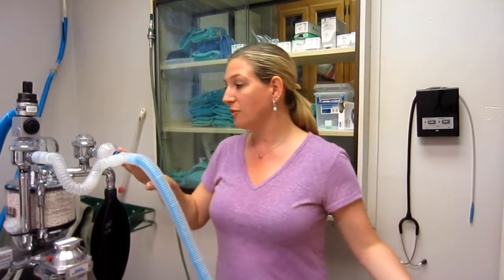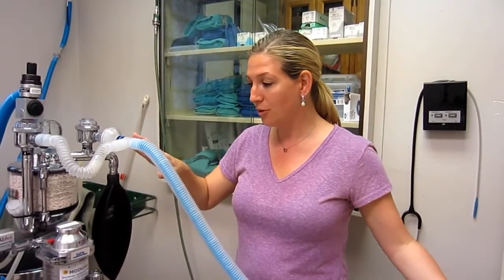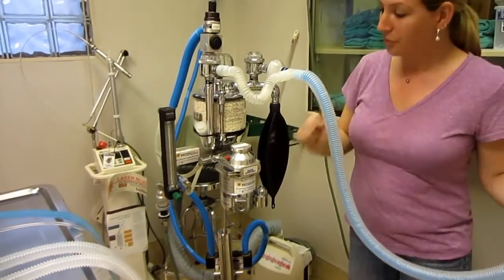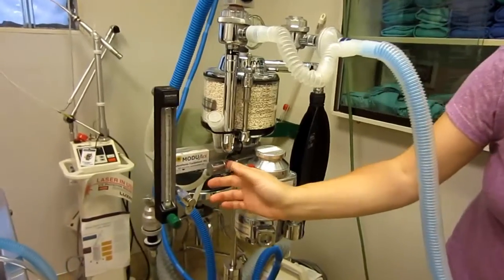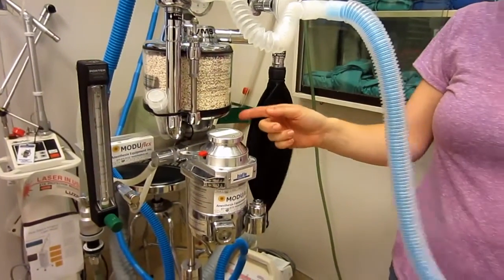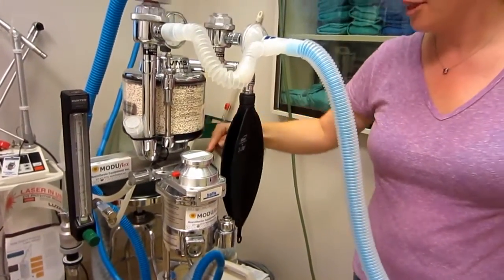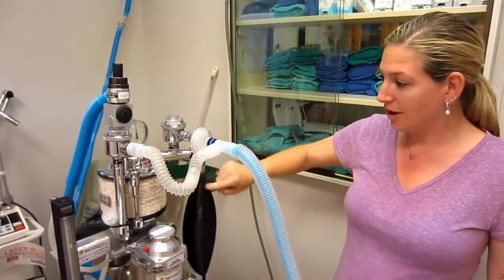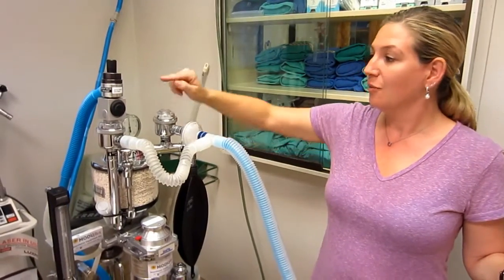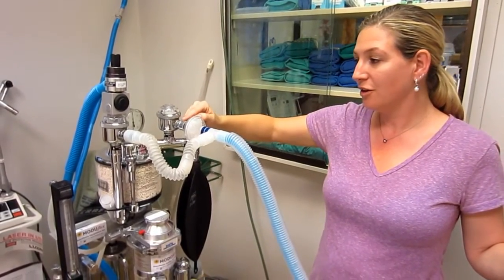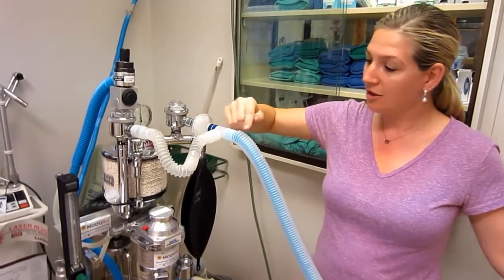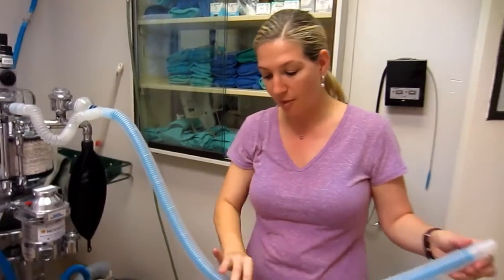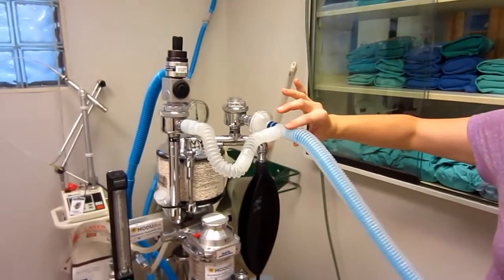But the way the recirculation system, the rebreathing system works is that the gas comes up through the flow meter. We go in the inlet, pick up our friend isoflurane, come out the outlet, up into the inhalation valve, as well as down into the reservoir bag. We go through our inhalation or unidirectional inhalation valve in our inhalation tube. We're delivered to our patient and rebreathed, and we come through the outside of the exhalation tube.